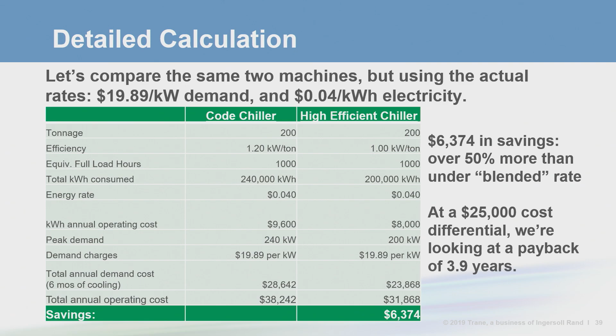Assuming the same 1,000 equivalent full load hours and 6 months of demand shift, we see that in reality, 2/3 of the total chiller's operating cost comes from that $19 demand charge. We get $4,700 in demand savings alone with the high efficiency option, plus another $1,600 from kWh savings. In total, we're saving over $6,300 a year in utility expense for the school. This is 53% more than we would have thought using that blended rate. So now the high efficiency chiller, which had a decent but marginal payback before, now has a much more attractive payback of 3.9 years. The school district is a whole lot more likely to want that high efficient machine now.